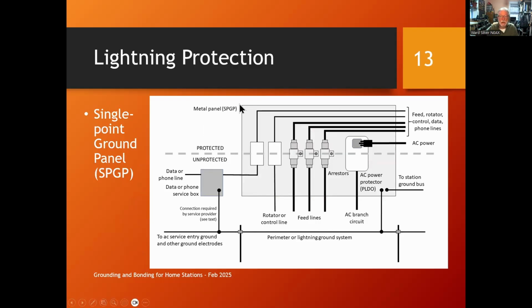You can see it flying around up here. Here's a single point ground panel. It's just a big piece of metal. Typically, it's a big piece of aluminum. And you mount all of your lightning arresters on that piece of aluminum. You mount a protector for your data or phone service. You mount a protector for your rotator or your control line. You even mount an AC power protector, sometimes called a protected line duplex output. And basically it has protectors in it.